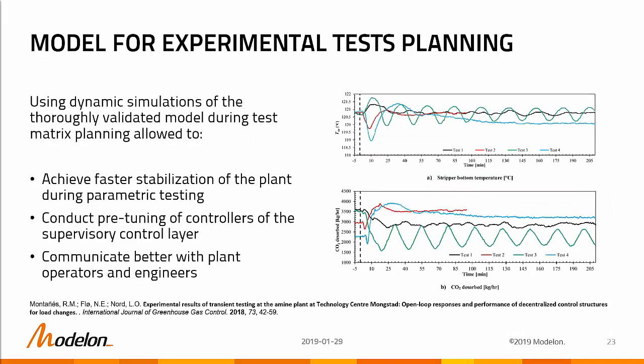We used this dynamic process model to prepare experimental tests, since we wanted to conduct tests at the real pilot plant and analyze the performance of different control structures. We used the model to prepare the test matrix, and we found it very useful, for example allowing faster stabilization of the plant during parametric testing, which saves money and time. It also allows pre-tuning of controllers in the supervisory control layer, and better communication with plant operators and engineers before and during the testing phase.